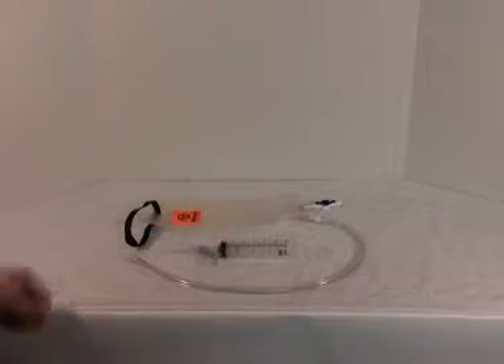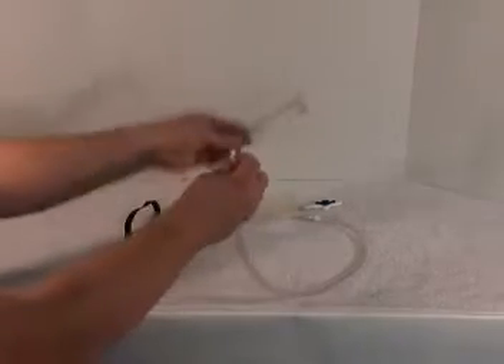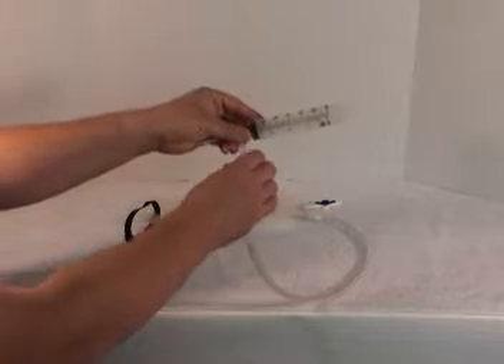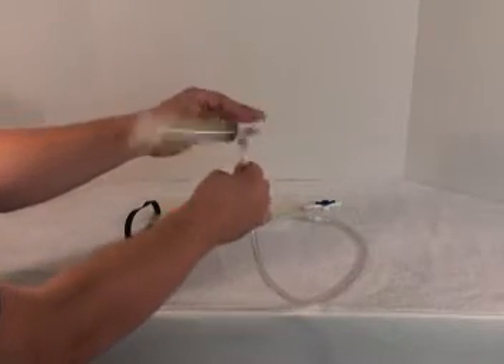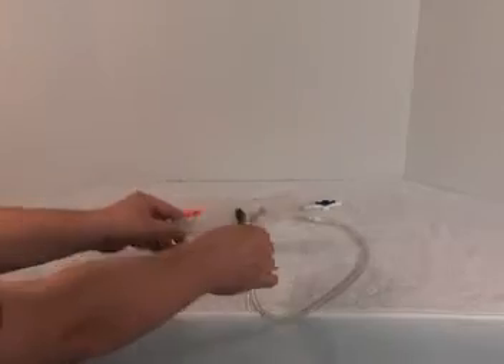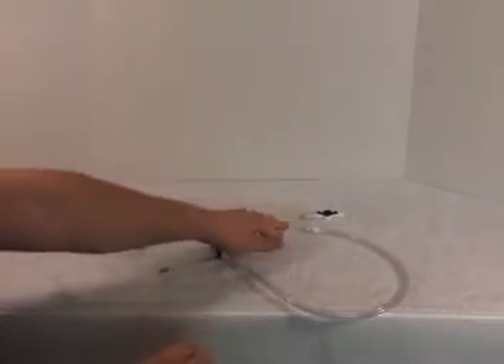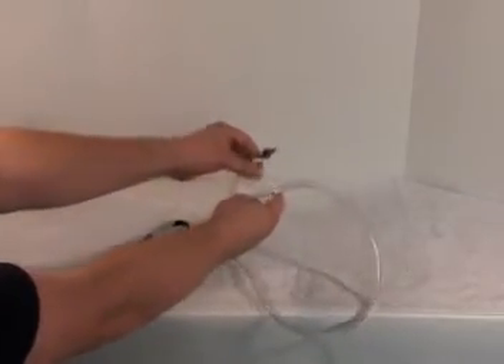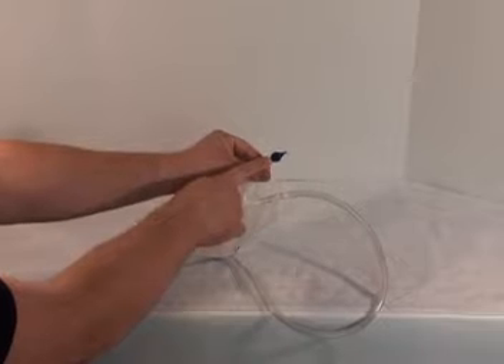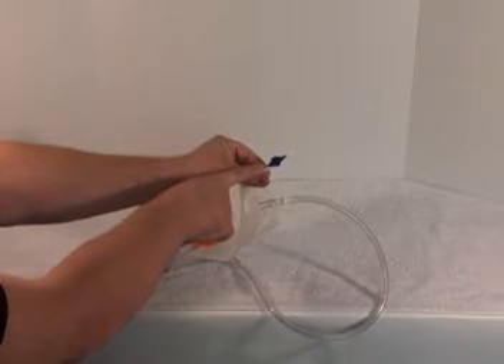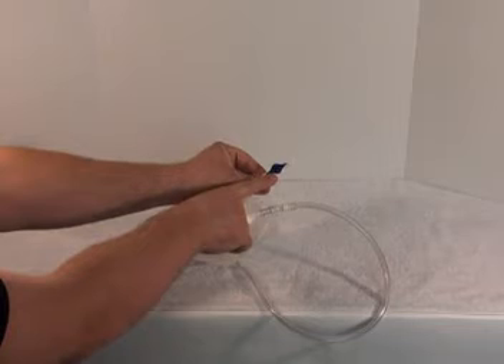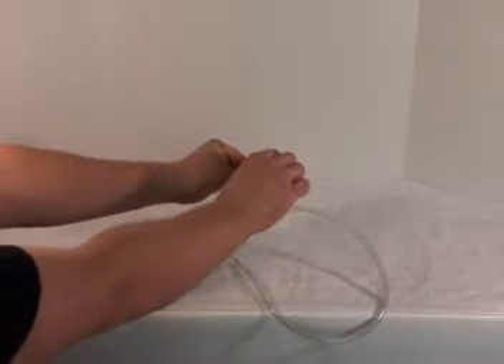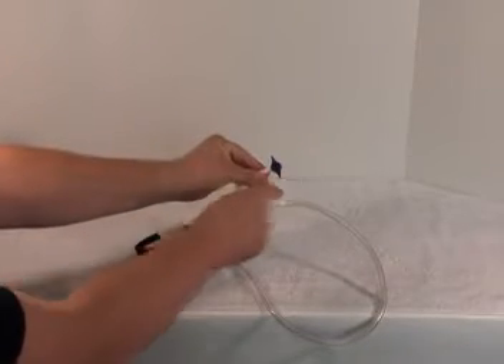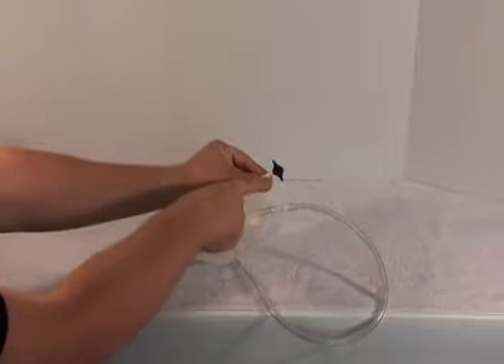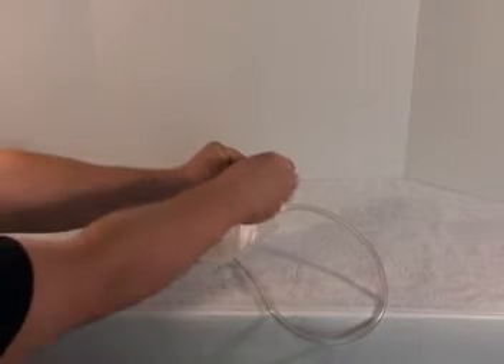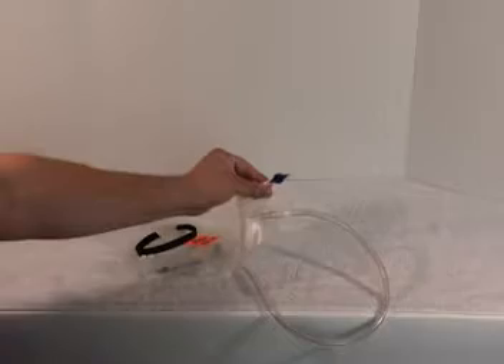Using UroPal is simple. First, assemble the device by screwing the tube into the syringe assembly. Second, make sure that the drainage bag valve is in the closed position. When it is in the closed position, the blue valve is in line with the white drainage tube. When it is open, it is 90 degrees from the white drainage tube. Please make sure that it is closed before UroPal is used.